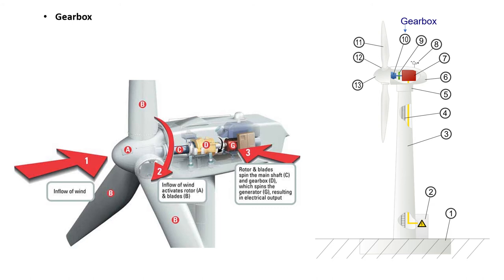Next in the list is the gearbox. In conventional wind turbines, the blades spin a shaft that is connected through a gearbox to the generator. The gearbox converts the turning speed of the blades — 15 to 20 rotations per minute for a large 1 megawatt turbine — into a faster 1800 revolutions per minute that the generator needs to generate electricity.